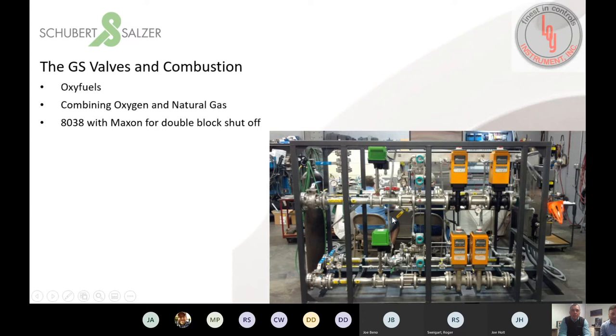Yeah, so this is a pretty typical gas train where you have the double block or double block and bleed Maxon safety shutoff valves for your gas line, and then you have your modulating control. In the past, a lot of customers had used butterfly valves with either Modutrol motors or another type of electric actuator in those applications. But what ends up happening is on butterfly valves, you really only get a control range of probably 75%, if that. Whereas on the sliding gate valve, which Greg is showing here, the rangeability of control is really over 100% of that valve travel.